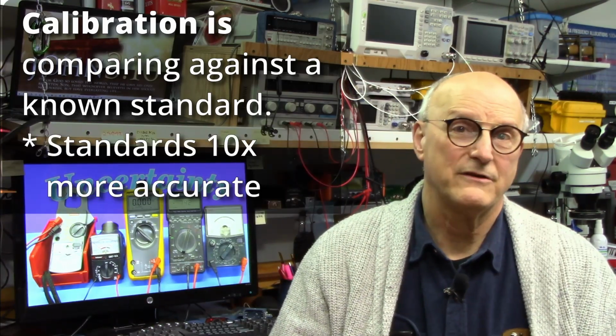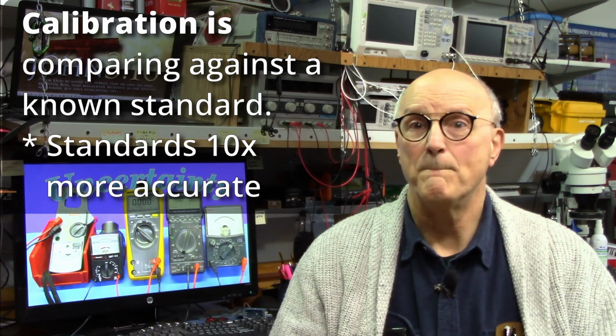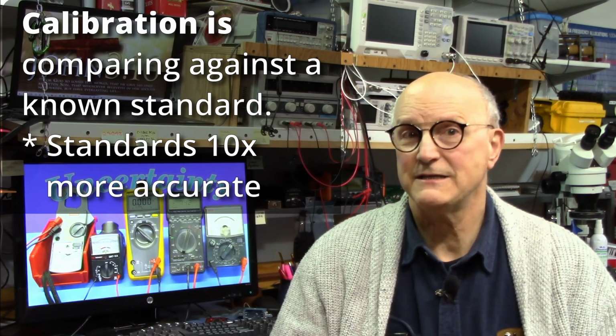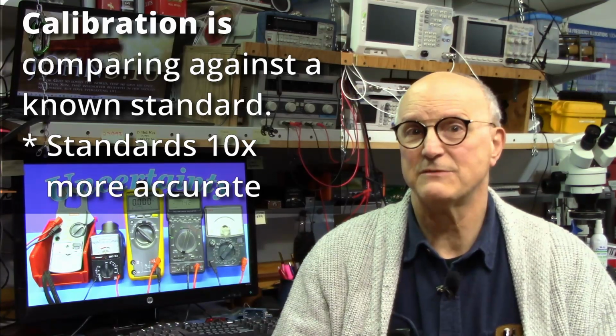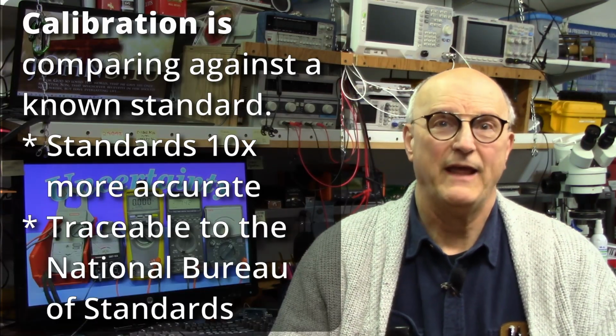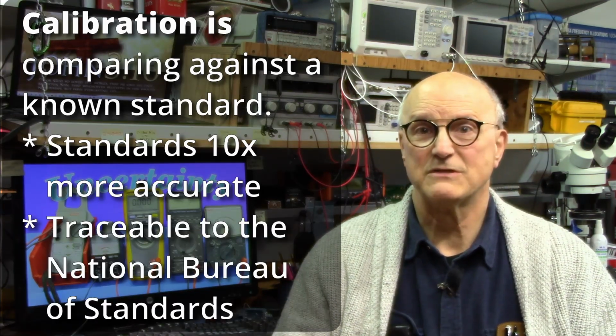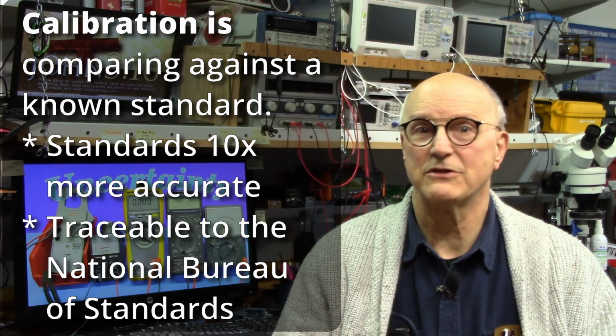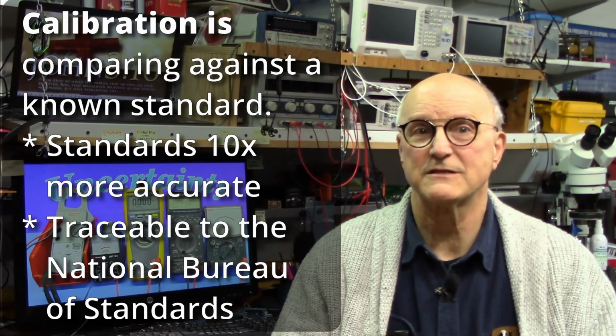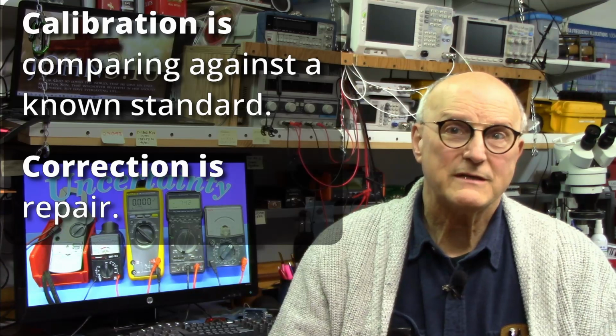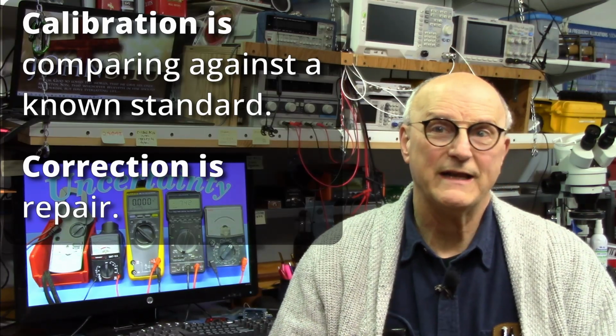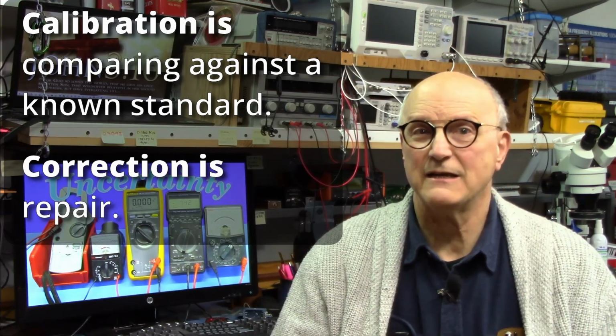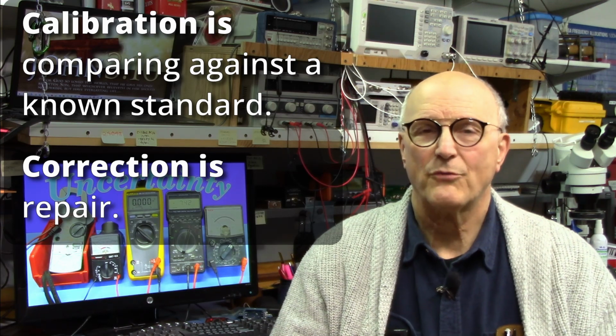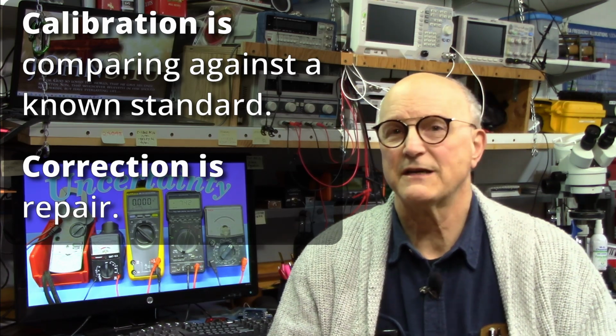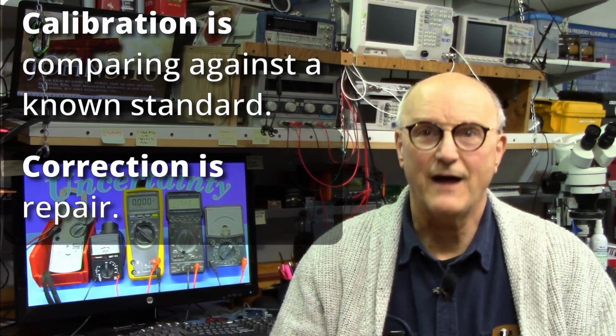The known standard against which it is compared must have an accuracy at least 10 times better than the device being calibrated. The accuracy of these known standards must be directly traceable to the National Bureau of Standards. If the measurement device that is being calibrated is outside its stated tolerance, then the correction of this condition is considered a repair, not calibration.